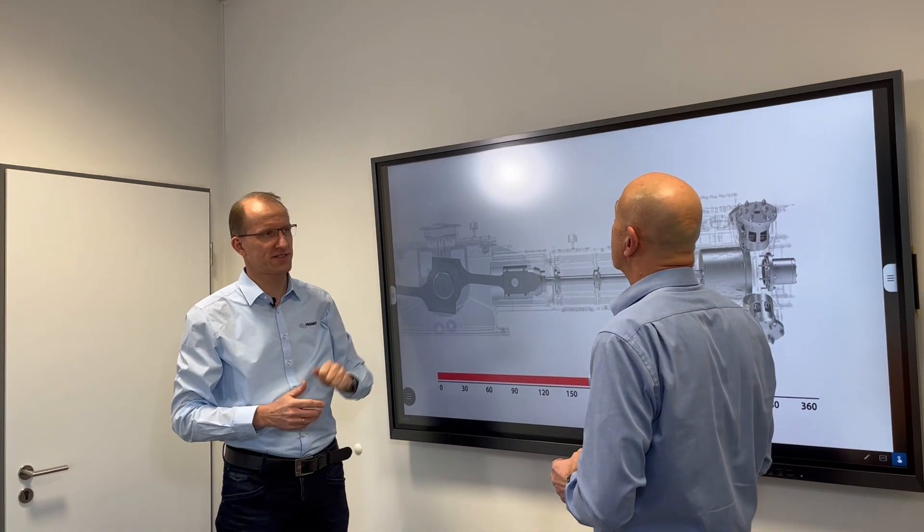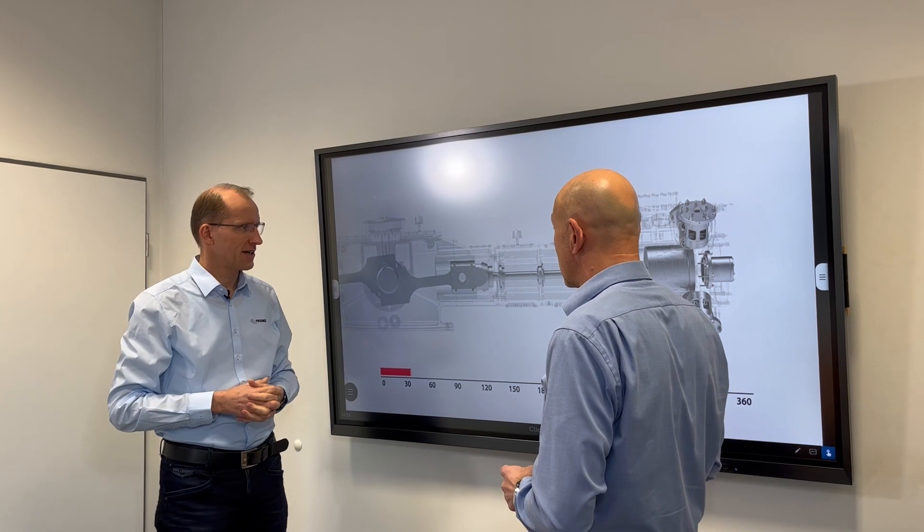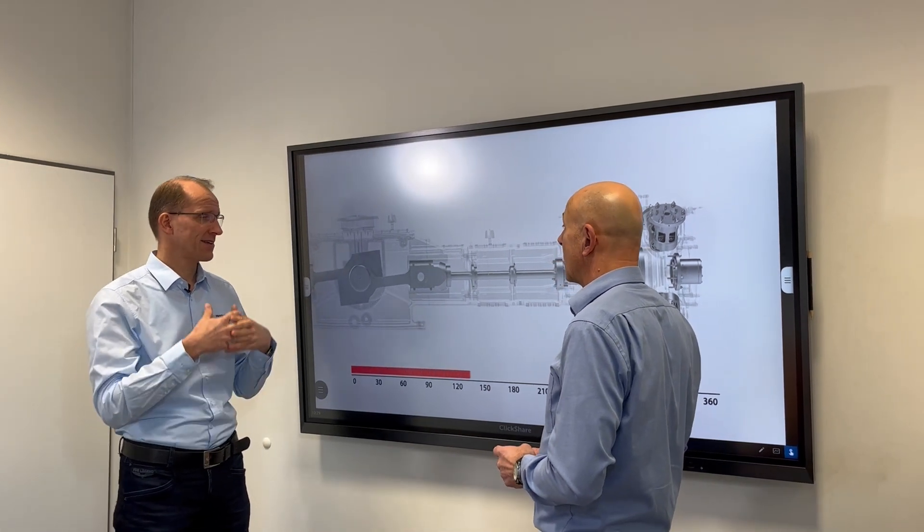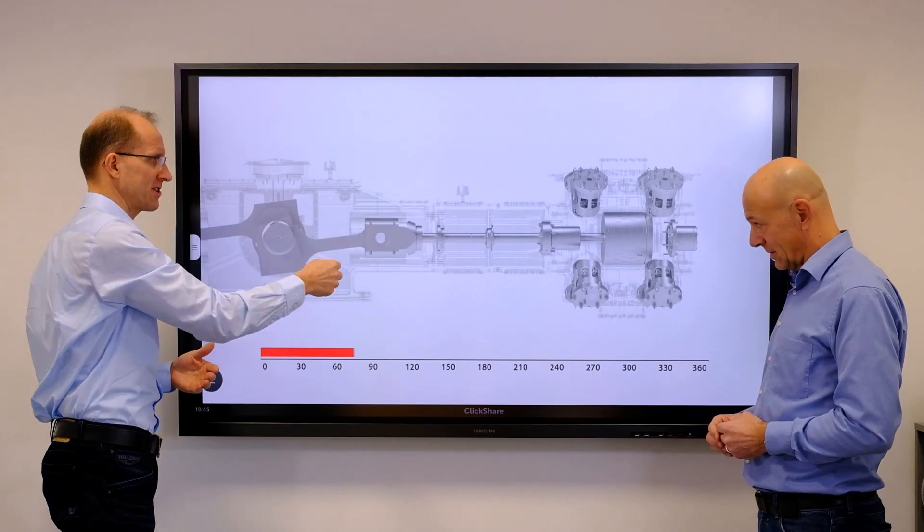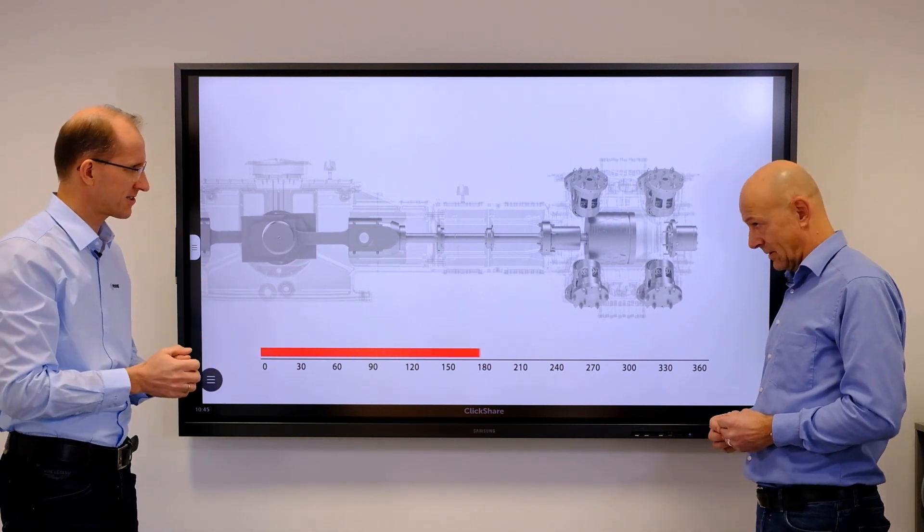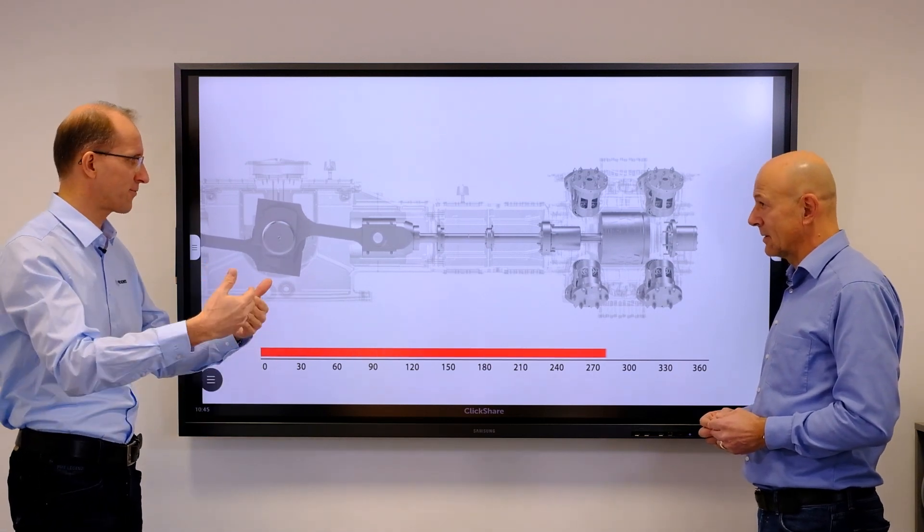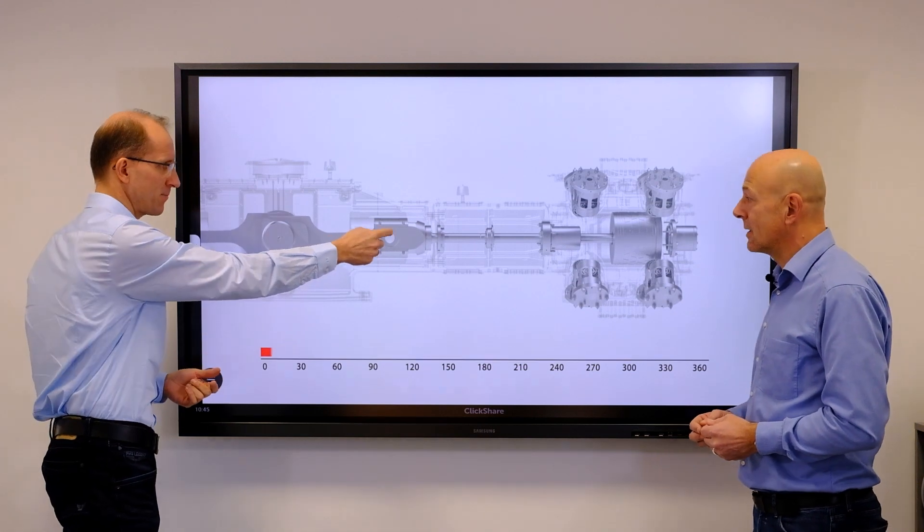What we could see is that the temperature is typically following the vibration. Because first, if the lubrication is lost, the pin seizing starts. Vibration and friction will then create a temperature increase.